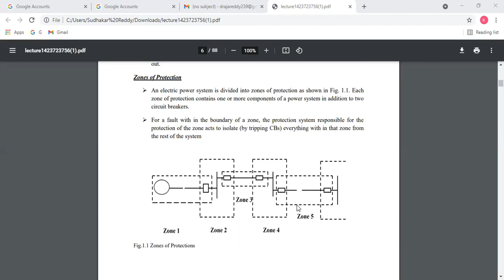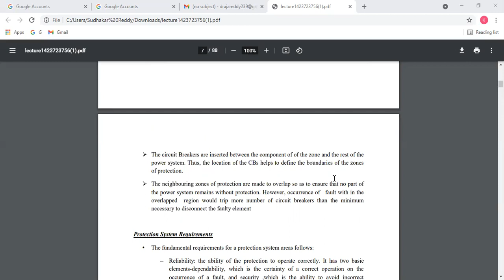The neighboring zones of protection are made to overlap to ensure that no part of the power system remains without protection. However, the occurrence of a fault within the overlapped region would trip more circuit breakers than the minimum necessary to disconnect the faulted element. Now, coming to the next point, protection system requirements.